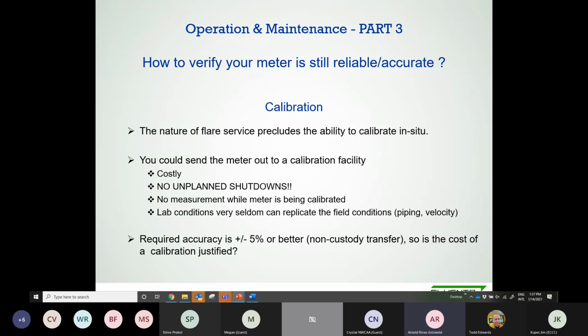Typically the required accuracy for these kinds of meters is plus or minus 5% or better, right? Usually it's not a custody transfer point of measurement, but because it's emissions, it's relevant, of course. So many companies sometimes aim for better than 5%. Typically our range out of the box goes from 2.5 to 5%. And if we need to do a calibration, we can take it down to 1% maybe. But again, it's going to be based on that velocity range that we can handle during the calibration. So just keep that in mind.